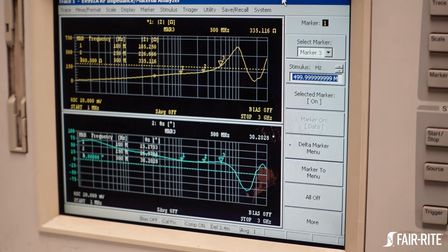Now, a kind of neat thing that these meters do, when you change the markers around on here, you can actually interpolate between the data points that it's actually measuring. So this is doing a similar thing of measuring about 200 data points between 1 megahertz and, in this case, 3 gigahertz. But you can set a marker, so as I'm scrolling through, it's hitting the individual data points that the machine's actually measuring. But if I want to hit something like, say, exactly 50 megahertz, we can do that, and it's going to give me the 50 megahertz reading because it's kind of filling in the blanks between the actual data measurement points.